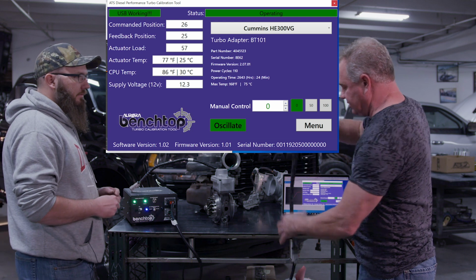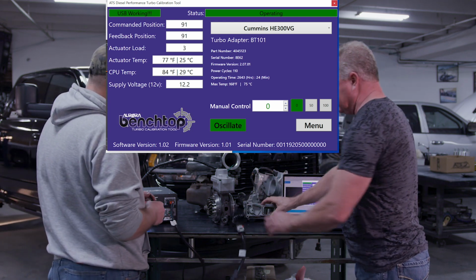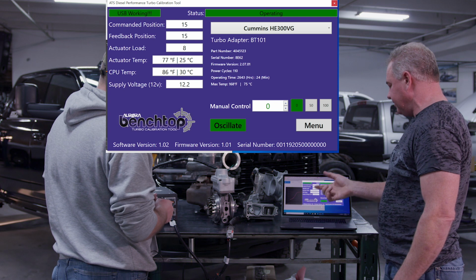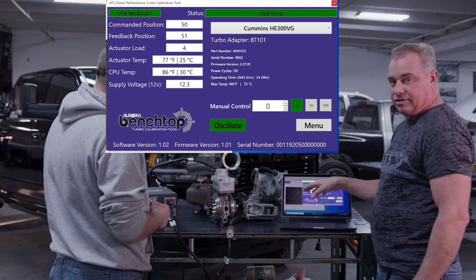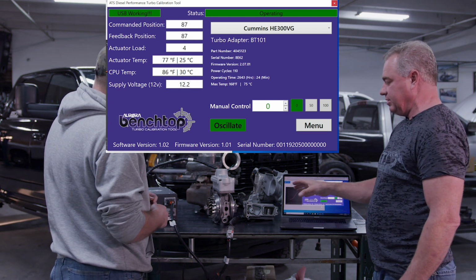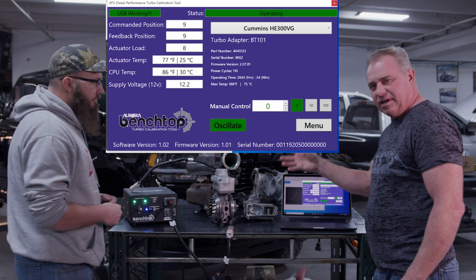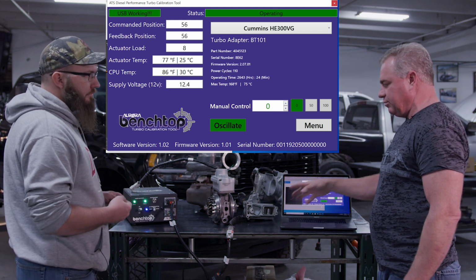So you kind of hear that. That basically is a sign of an actuator that's beginning to fail. So even though it's sweeping 0 to 100%, which we're going to show you as we calibrate it, even though it's completely sweeping, that one's vibrating, buzzing, making some noise - you hear the bearings going out. So probably stay away from that.